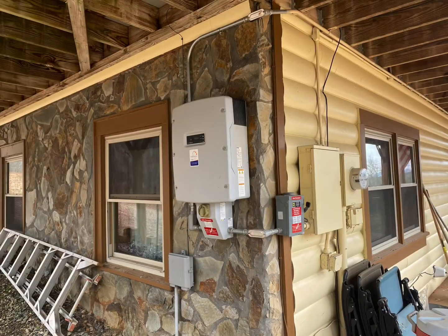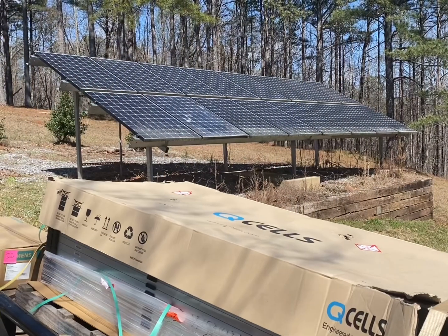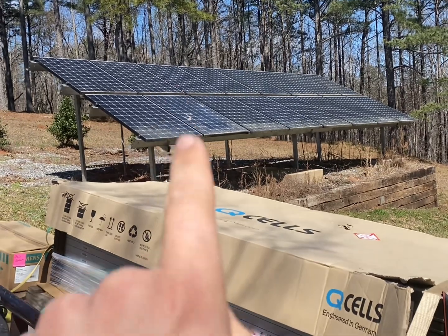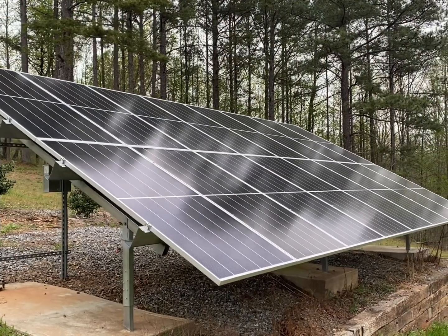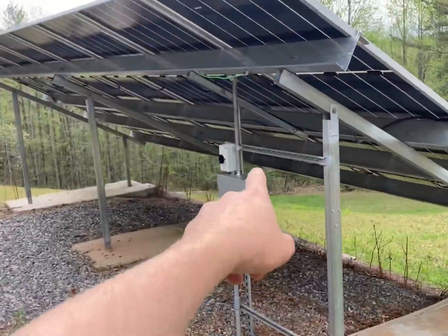This video is about putting a Solark outside. This is the first time I've actually done it. The reason I did it is the customer already had a system that was basically under the porch and under cover. It was an older system, had some broken panels as you can see right there, and it needed some repairs. So we changed out his panels, did a little bit of rewiring, and then came in to add the battery backup Solark system.